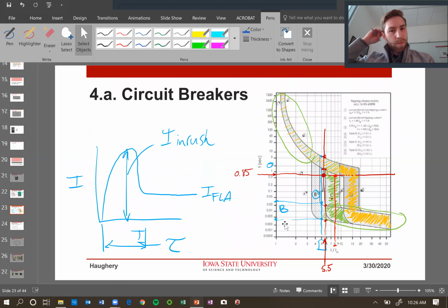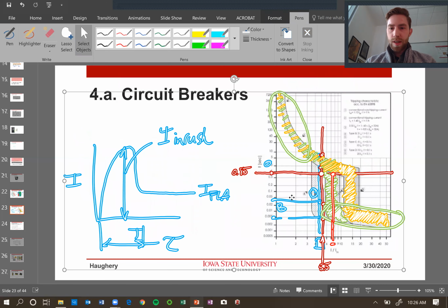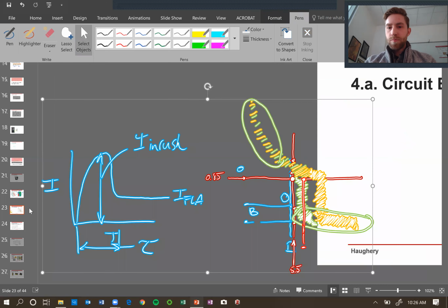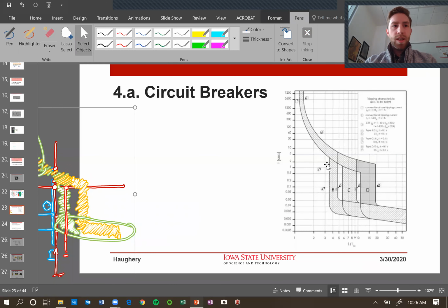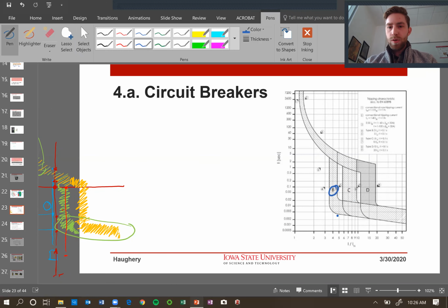This is a typical trip curve with multiple types. So we had a B, which will trip fairly quickly. A C will take a little bit longer to trip, and a D even longer to trip, given the same amount of current, say 5 times or 3 times or 10 times. And so we can decide what type of circuit breaker we use based on how long we want to hold the circuit breaker from tripping.